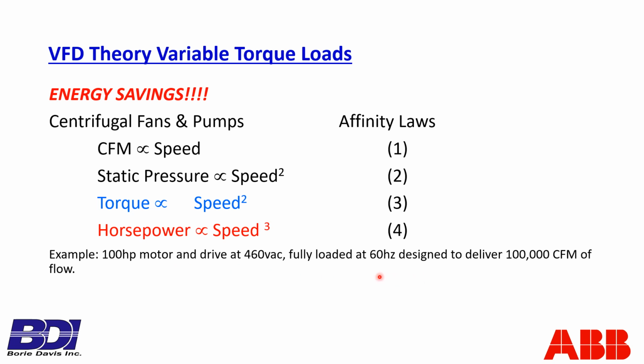But if I reduce the speed to 30 hertz and deliver 50,000 CFM of flow, I will need 50% speed cubed, which is 0.5 times 0.5 is 0.25 times 0.5 is 12.5%, 0.125. The power required to deliver 50% speed, 50% flow, is 12.5 horsepower on a 100 horsepower application. That is a lot of energy savings.